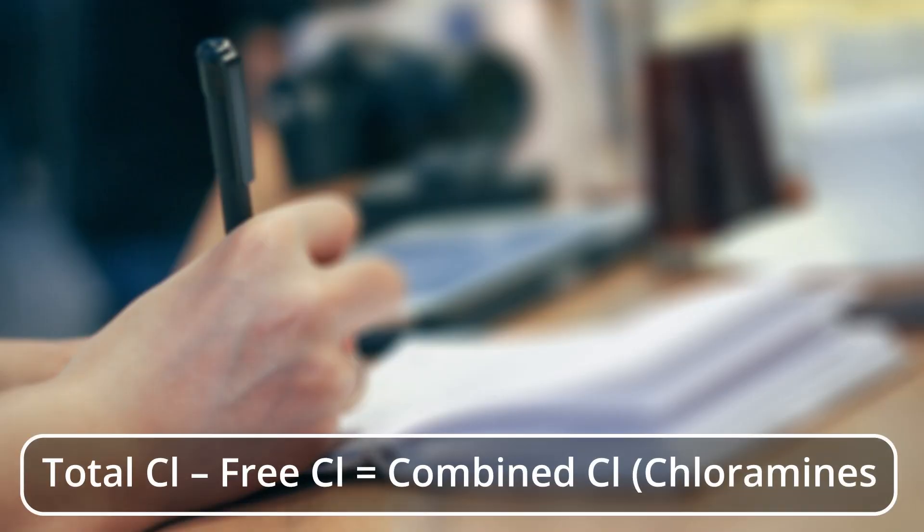Chloramines are usually measured as combined chlorine residual. You find this by subtracting the free chlorine residuals from the total chlorine residual. Total chlorine minus free chlorine equals combined chloramines.